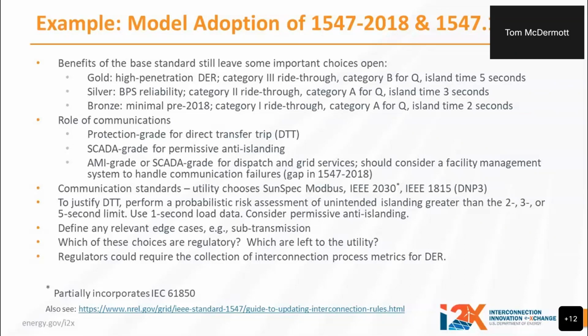The role of communications is important. What you're using it for, direct transfer trip, tends to be an expensive cost item for an interconnection study when it's required. There are some gaps, we think, in IEEE 1547 2018, and what happens if there's communication failure and the DER is relying on some central dispatch function for control of real and reactive power. What happens then? The utility right now chooses between 3 options: the SunSpec Modbus, the IEEE 2030, which some people will say is really IEC 61850. It isn't exactly, but it does incorporate the logical object model from IEC 61850, and then DNP3, which is of course now an IEEE standard.